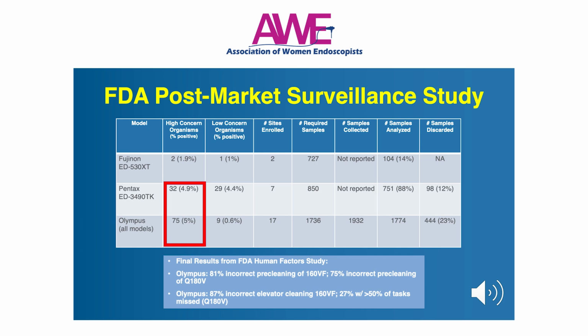This is a post-market surveillance study that was commissioned by the FDA to see how often contamination was seen after high-level disinfection of duodenoscopes. And while they expected a 0.4% rate, they actually found something closer to 5%, which is about 13 times what they expected. They also found in a human factor study numerous cases where there were incorrect steps in terms of pre-cleaning. In many cases, in fact, more than half the steps would even be missed on some devices.